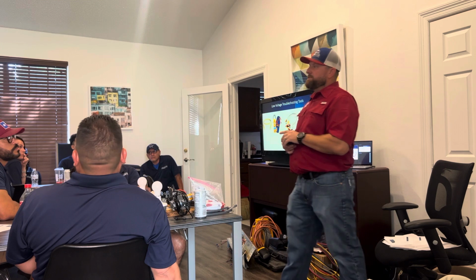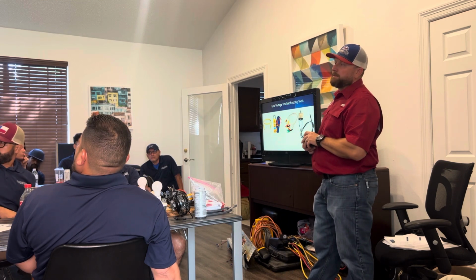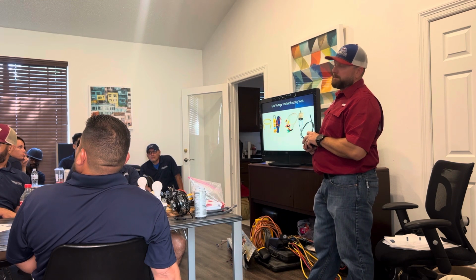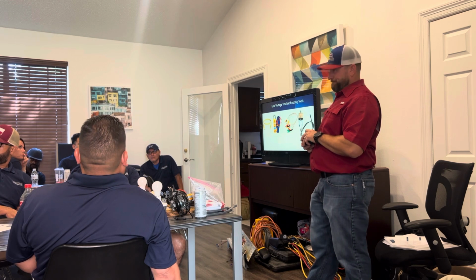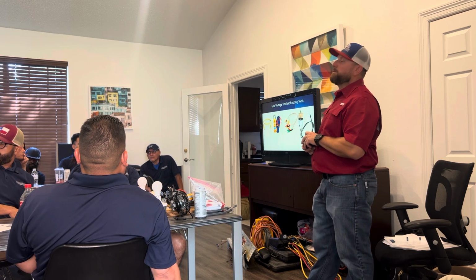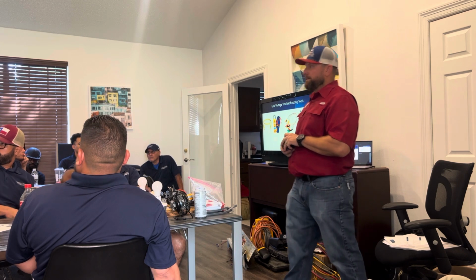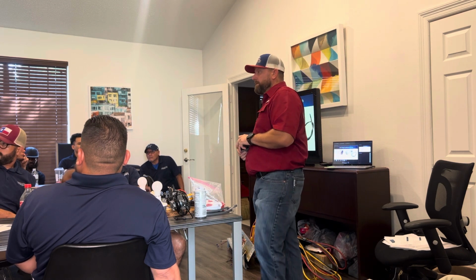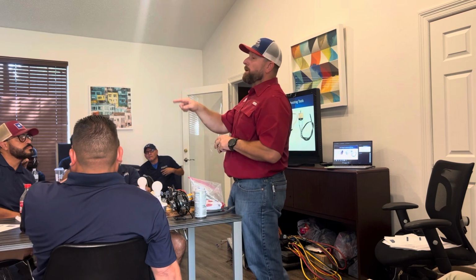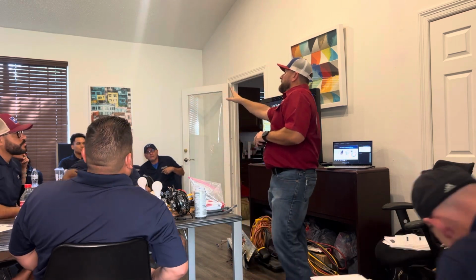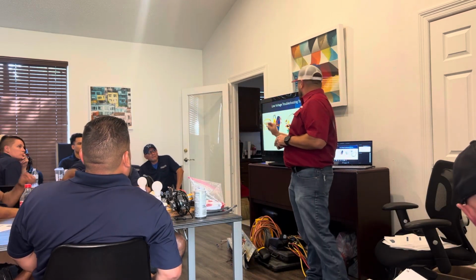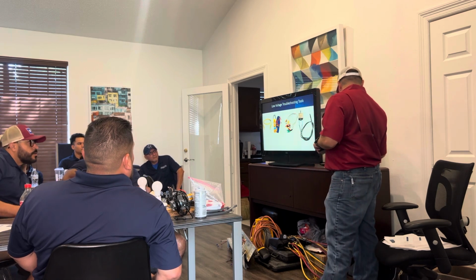Anything else? You got a question? Yeah, one thing that you mentioned is that the common connection of the thermostat on our units comes straight from the transformer out to the unit. Yes, for the new guys. Because they're gonna go crazy looking for the common wire on the thermostat. That is a good point, very good point. Did y'all catch that? A lot of thermostats will not have the common wire to it.